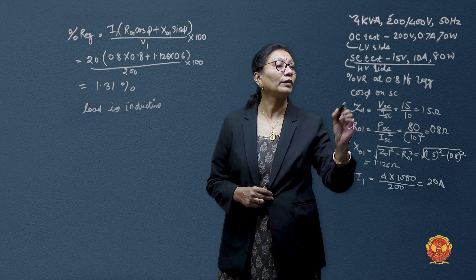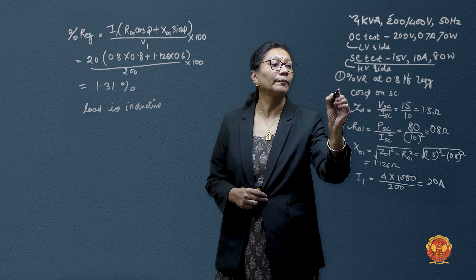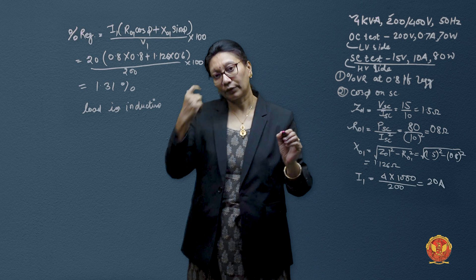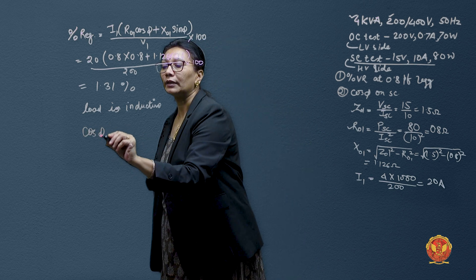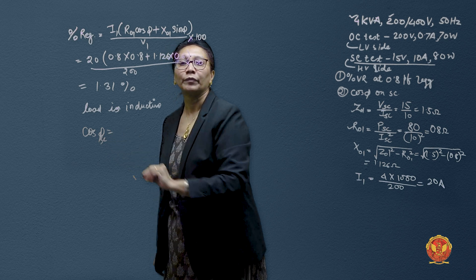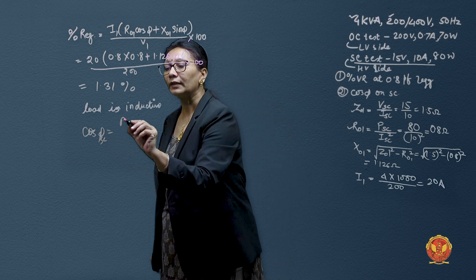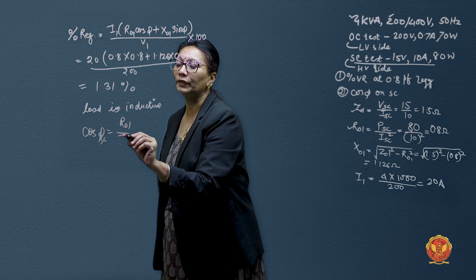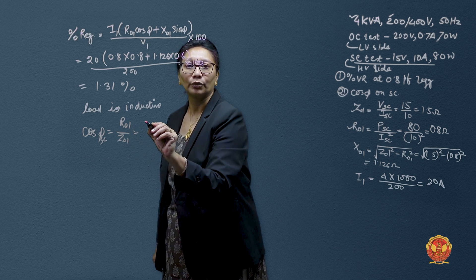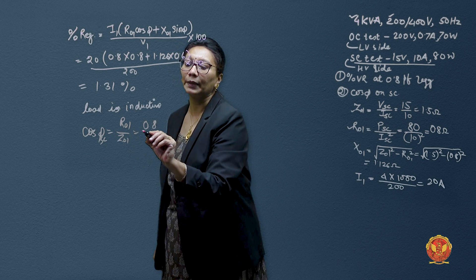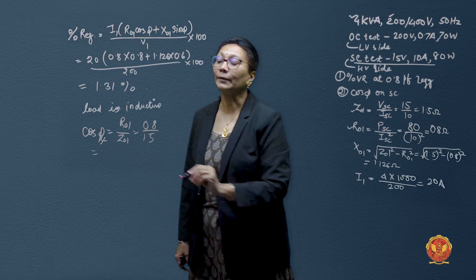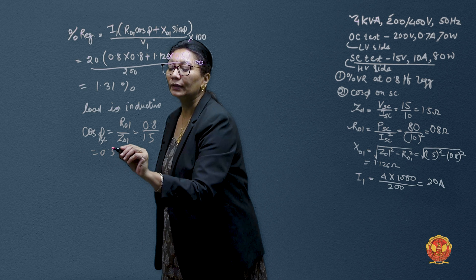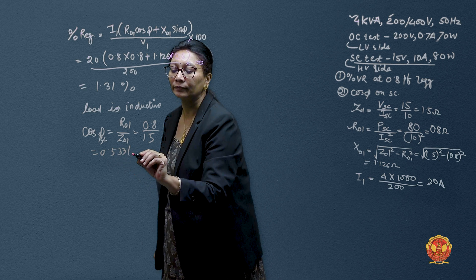But next what we had to calculate, one was this. Second, we have to find power factor in short circuit case. So power factor can be calculated in short circuit as R by Z. And both we have already calculated. So this would be 0.8 divided by 1.5. And therefore, power factor comes out to be 0.533 lagging.